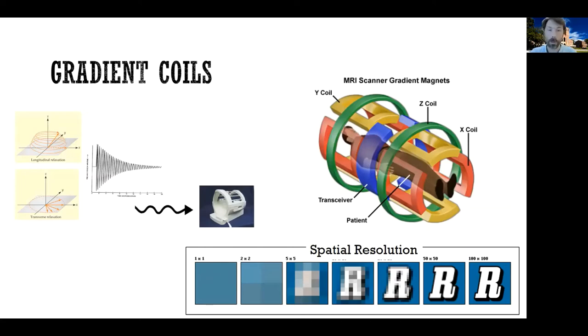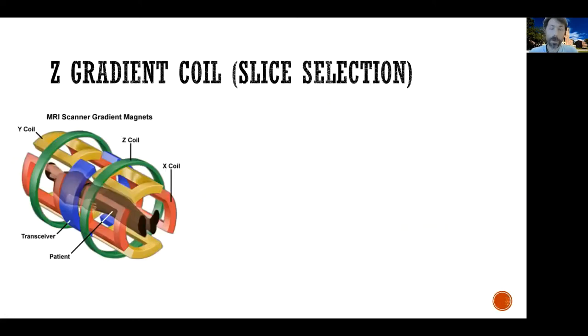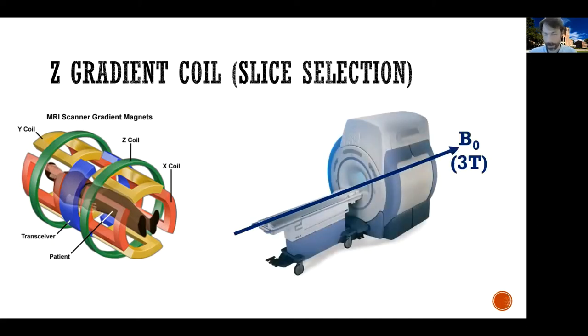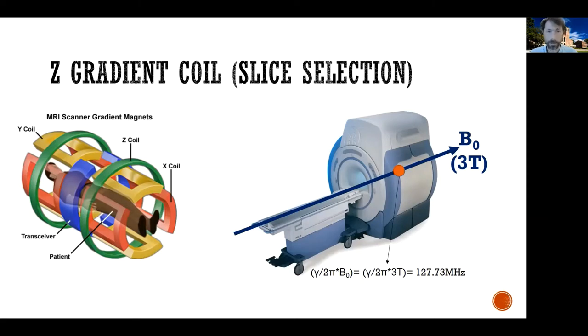There are three gradient coils, one per direction. There's a gradient coil for the Z direction, one for X, and one for Y. The first is often referred to as the slice selection gradient coil, typically in the Z direction — from feet to head. Now, take our MRI machine: in the typical research case they are at three Tesla. From the Larmor equation, you know the resonating frequency is the gyromagnetic constant over two pi times the strength of the magnetic field.